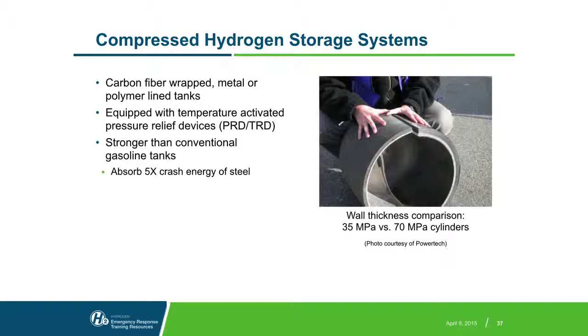That means that the PRD has to see heat, and there's a fusible plug that will melt open and vent the contents of the tank. So they're not intended to seal back at a certain pressure. Once they're opened, they're venting the contents.